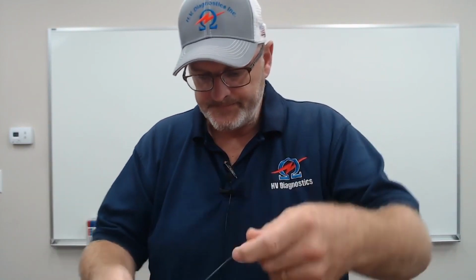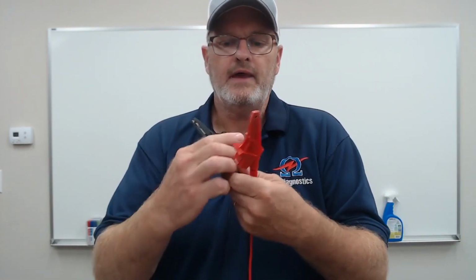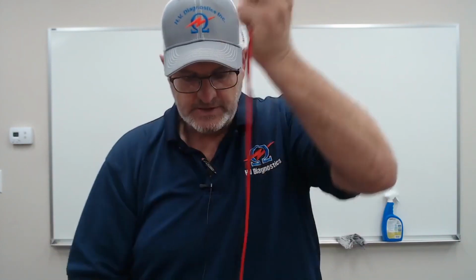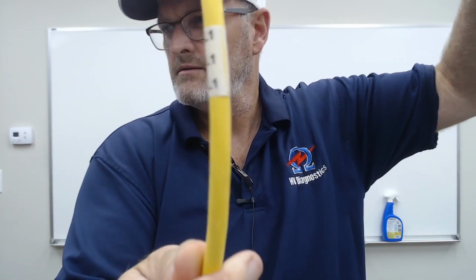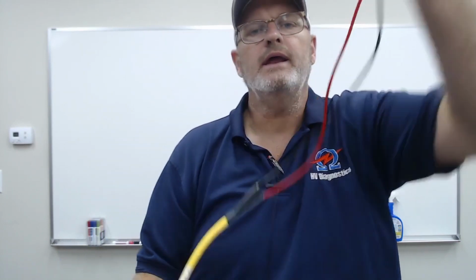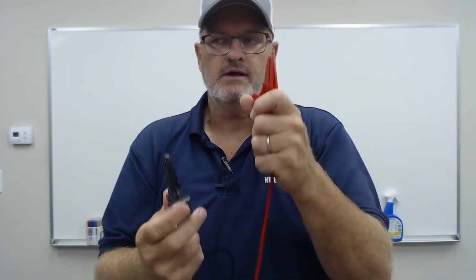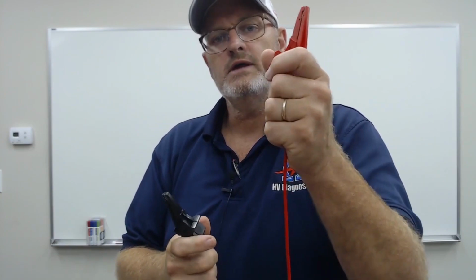In addition to that, we could hook up directly onto the cable. If we hook up directly onto the cable, we use this lead over here that we plug into the transmitter. And then these leads over here will connect, the black cable will go onto C phase, and the red cable will go onto A phase or B phase. This particular cable is L1. If you look over here, so let me turn that around, L1. So that will connect onto C phase here and A phase over here.